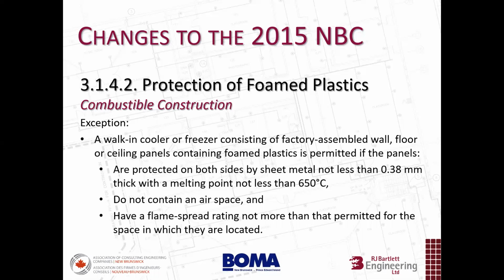An exception to combustible construction for the methods we just looked at for separating is a walk-in cooler or freezer consisting of factory assembled wall, floor, and ceiling panels containing foam plastics. These are permitted, provided they are protected on both sides by sheet metal not less than 28 gauge thick, with a melting point of not less than 650 degrees Celsius. No air spaces, so they have to be sandwiched. The foam plastic has to be sandwiched completely, and have a flame spread rating not more than that permitted for the space in which they are located.